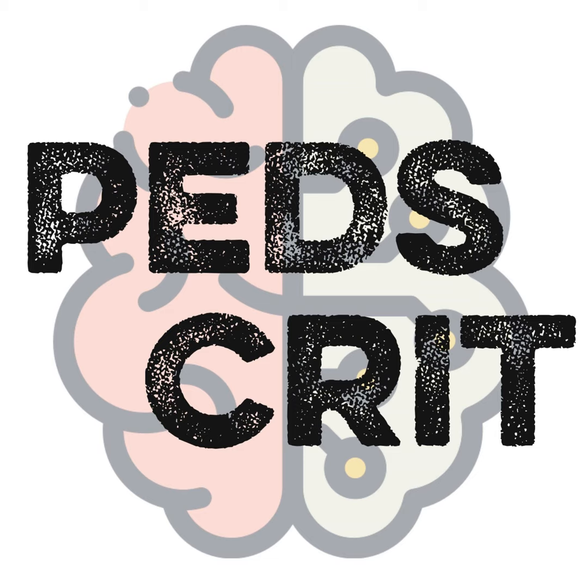Nice. And the flow sensor, to make it a little more sensitive, you would make it a smaller number, and to make it less sensitive, you make it a bigger number. Exactly. Yeah. So less flow is needed to trigger the breath. So we talked about if the ventilator is not sensitive enough to detect that breath and we have mistriggering. What if our ventilator is set too sensitively, where it's picking up maybe things that aren't breaths?